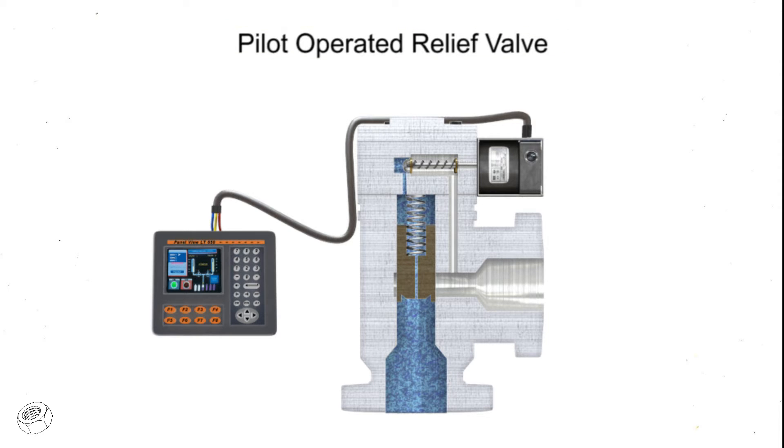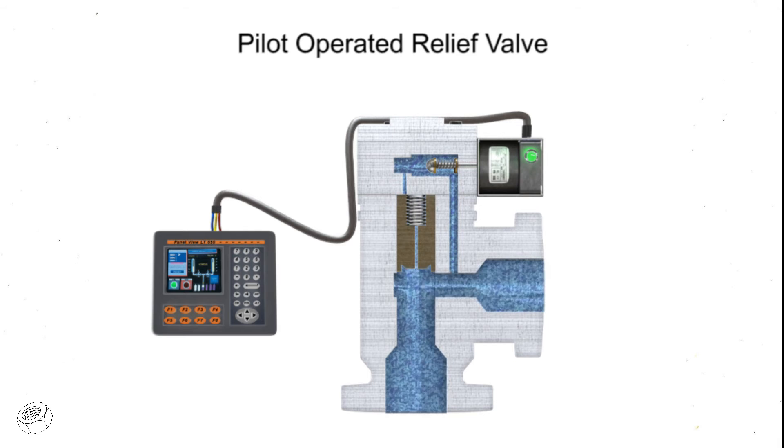When the solenoid is energized, the core opens the pilot orifice and relieves pressure from the top of the valve piston or diaphragm to the outlet side of the valve. This results in an unbalanced pressure, lifting the piston or diaphragm off the main orifice. When the solenoid is de-energized, the pilot orifice is closed and full line pressure is applied to the top of the piston or diaphragm, closing the valve.